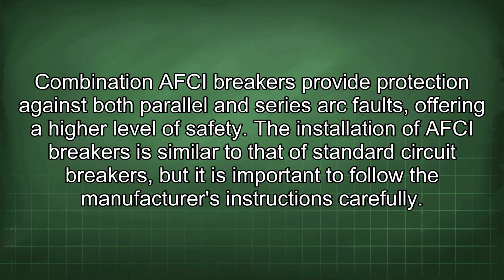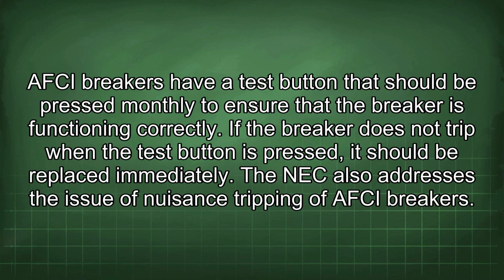The installation of AFCI breakers is similar to that of standard circuit breakers, but it is important to follow the manufacturer's instructions carefully. AFCI breakers have a test button that should be pressed monthly to ensure that the breaker is functioning correctly. If the breaker does not trip when the test button is pressed, it should be replaced immediately.